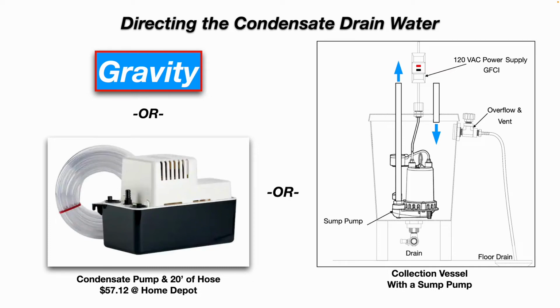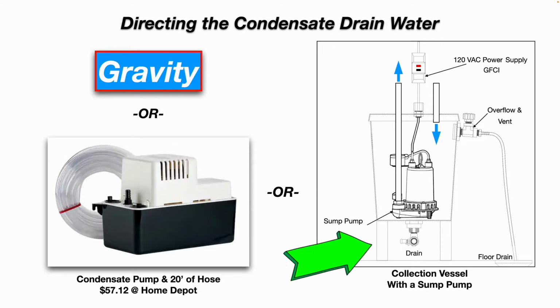Or a third option, you can make your own collection vessel and install a sump pump inside of it. In this example, we are using a 5-gallon bucket that is elevated on some 2x6 wooden, basically like a little wooden platform. And you can see we have a 120 volt AC power supply, GFCI protected, providing power to our sump pump. Our sump pump is controlled by a float switch. As the condensate water fills up the 5-gallon bucket, again, the float floats up, turns the pump on, and the pump will discharge the water out the discharge tube to where you want it to go.